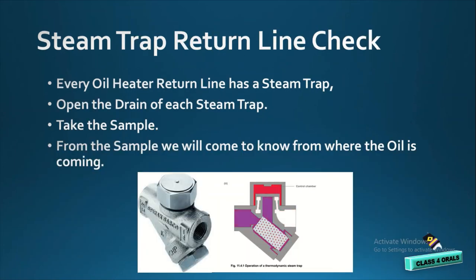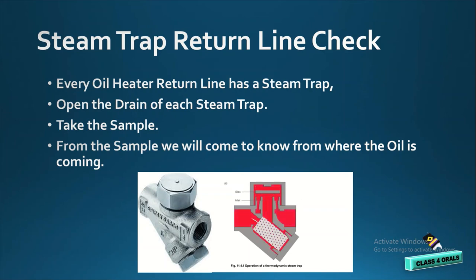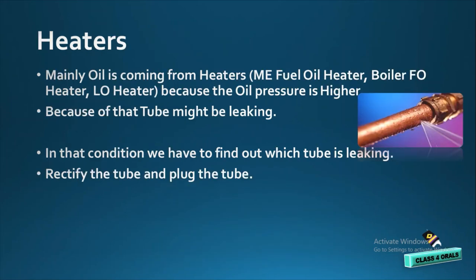Now, we have to check the steam trap return line. Every oil heater return line is having a steam trap. We have to open the drain of each steam trap, take the sample from that. From that sample, we will come to know from where the oil is coming into the hot well.